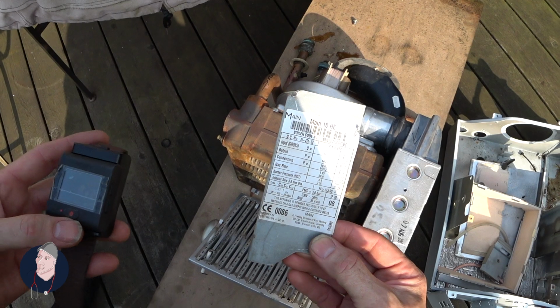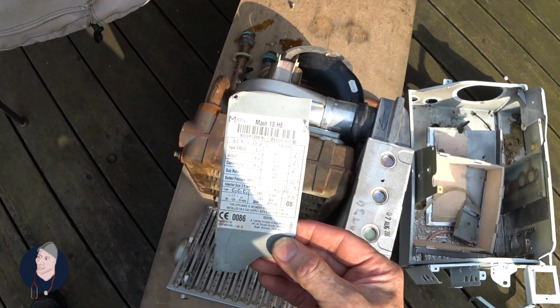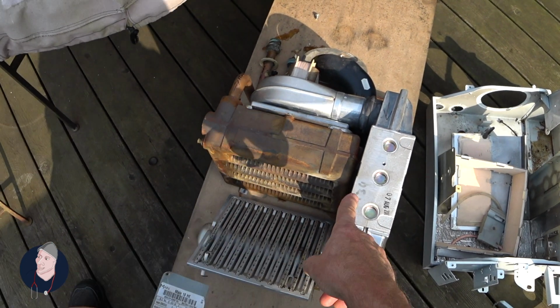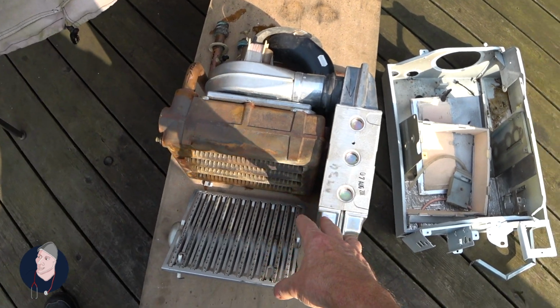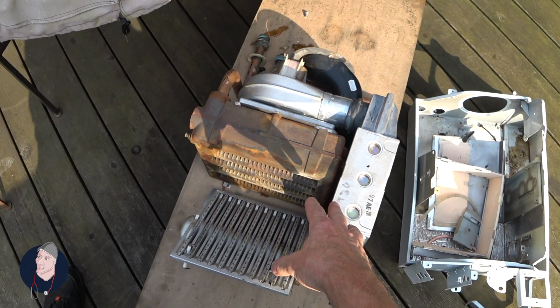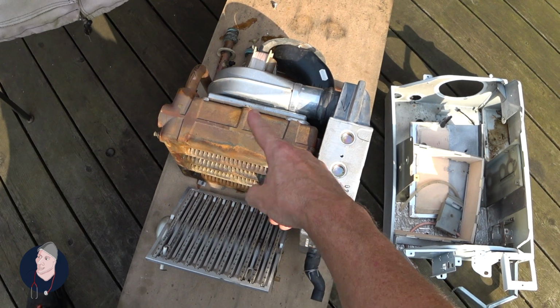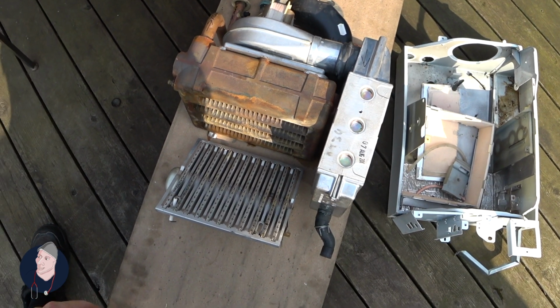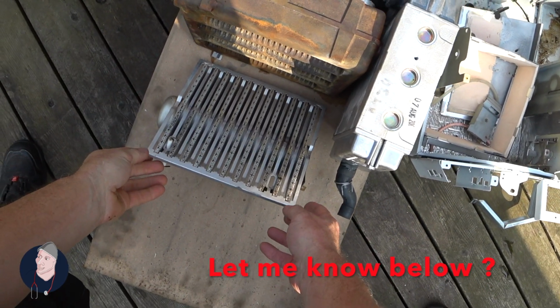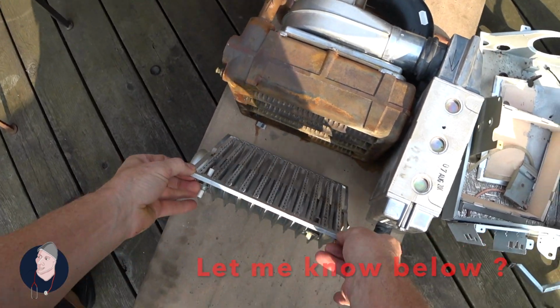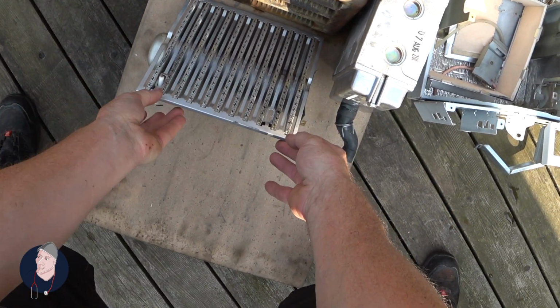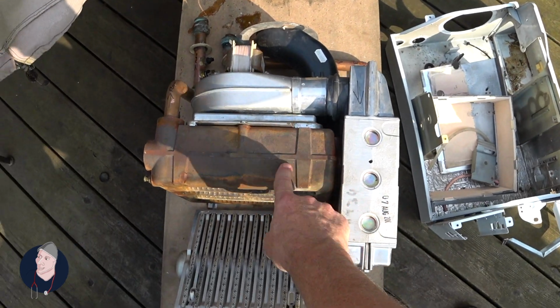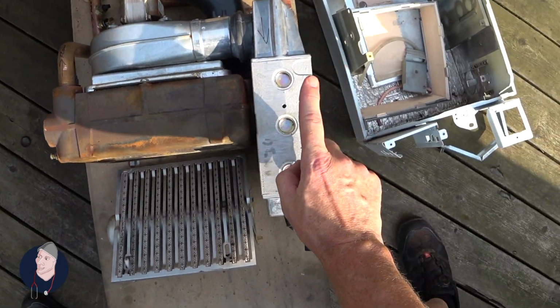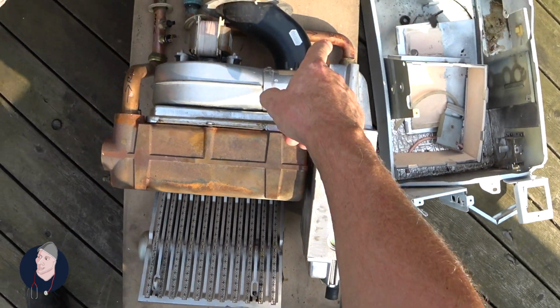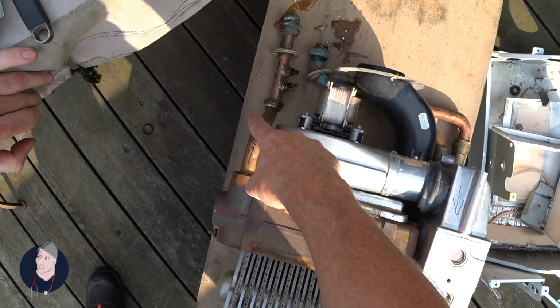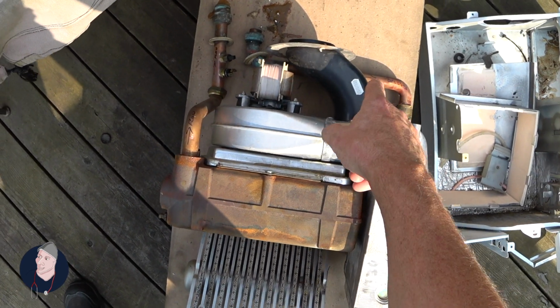So this is a quick overview of the main 18HE. This is the assembly for the main heat exchanger. I think if I'm right, this was a B rated boiler. So simply gas burner down at the bottom, main heat exchanger, secondary heat exchanger, fan, flow and return.